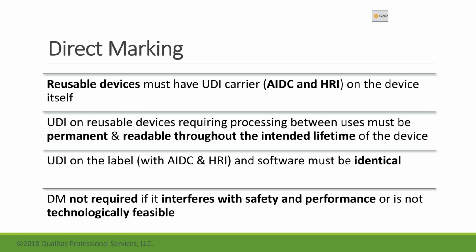The UDI, again, I mentioned this on the previous slide, a UDI on the label of software packaging as well as the software must be identical. And then the direct marking is not required if it interferes with safety and performance or is not technologically feasible. This is the same with the FDA as well.